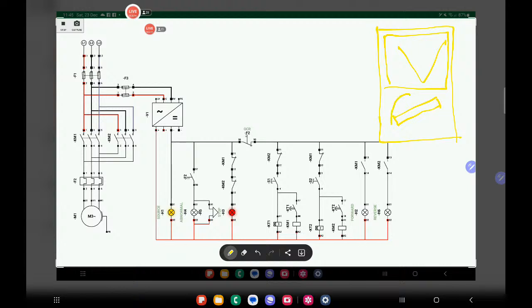So this is a safety precaution, right? The best way to check your panel is, regardless if you know the output voltage or the voltage of that system, even if you are sure it is 24 volts, you still need to use AC. You need to put your selector onto the AC of your multimeter and try to measure if it is AC or DC. Double check or triple check your system first, unless you are the one who did the control panel itself, because you'll never know, maybe it's also an AC or there is a problem on the system and it's still an alternating current on your system, no? So you'll need to measure both lines if it is AC.